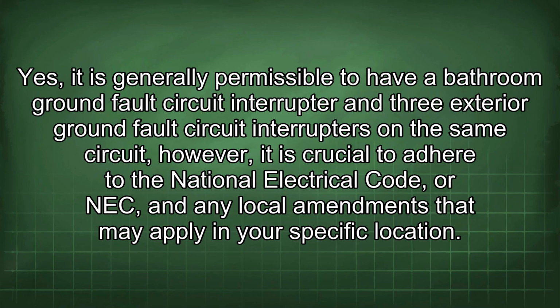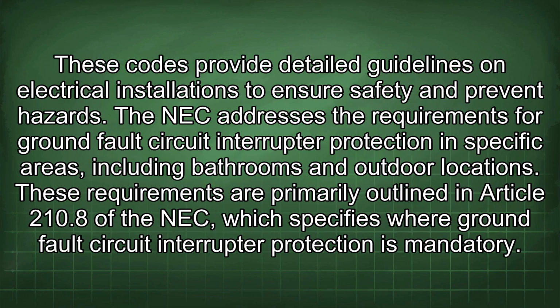Yes, it is generally permissible to have a bathroom ground fault circuit interrupter and 3 exterior ground fault circuit interrupters on the same circuit. However, it is crucial to adhere to the National Electrical Code, or NEC, and any local amendments that may apply in your specific location. These codes provide detailed guidelines on electrical installations to ensure safety and prevent hazard.